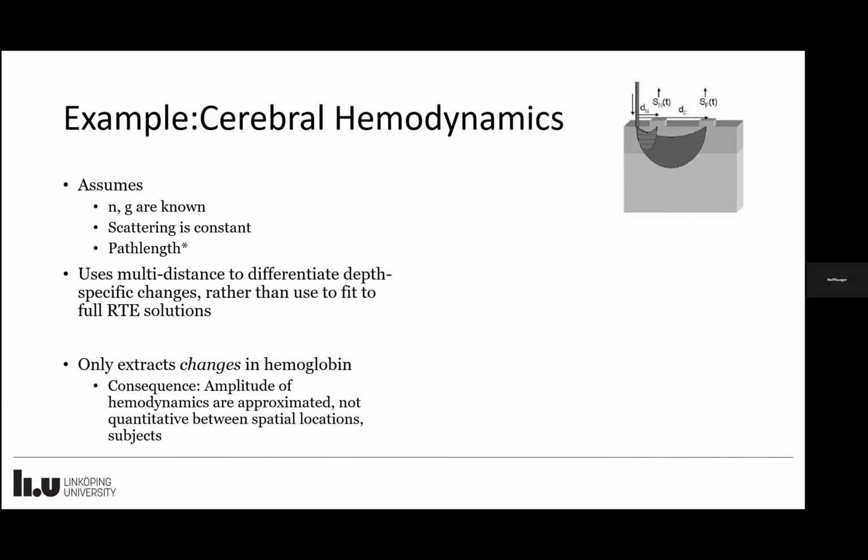And we made general assumptions on path length, but the important part of our technique is we recognize that everyone's skull, everyone's scalp, the size of everyone's head is different. Different locations are also going to have different thicknesses. So what we were developing was an adaptive method to really relate the two signals and scale them automatically for any geometric variation in that patient itself. And so that's where we actually used the temporal fluctuations as a kind of lock-in signal of the superficial versus the deep, and used that to adjust for all the geometric parameters.